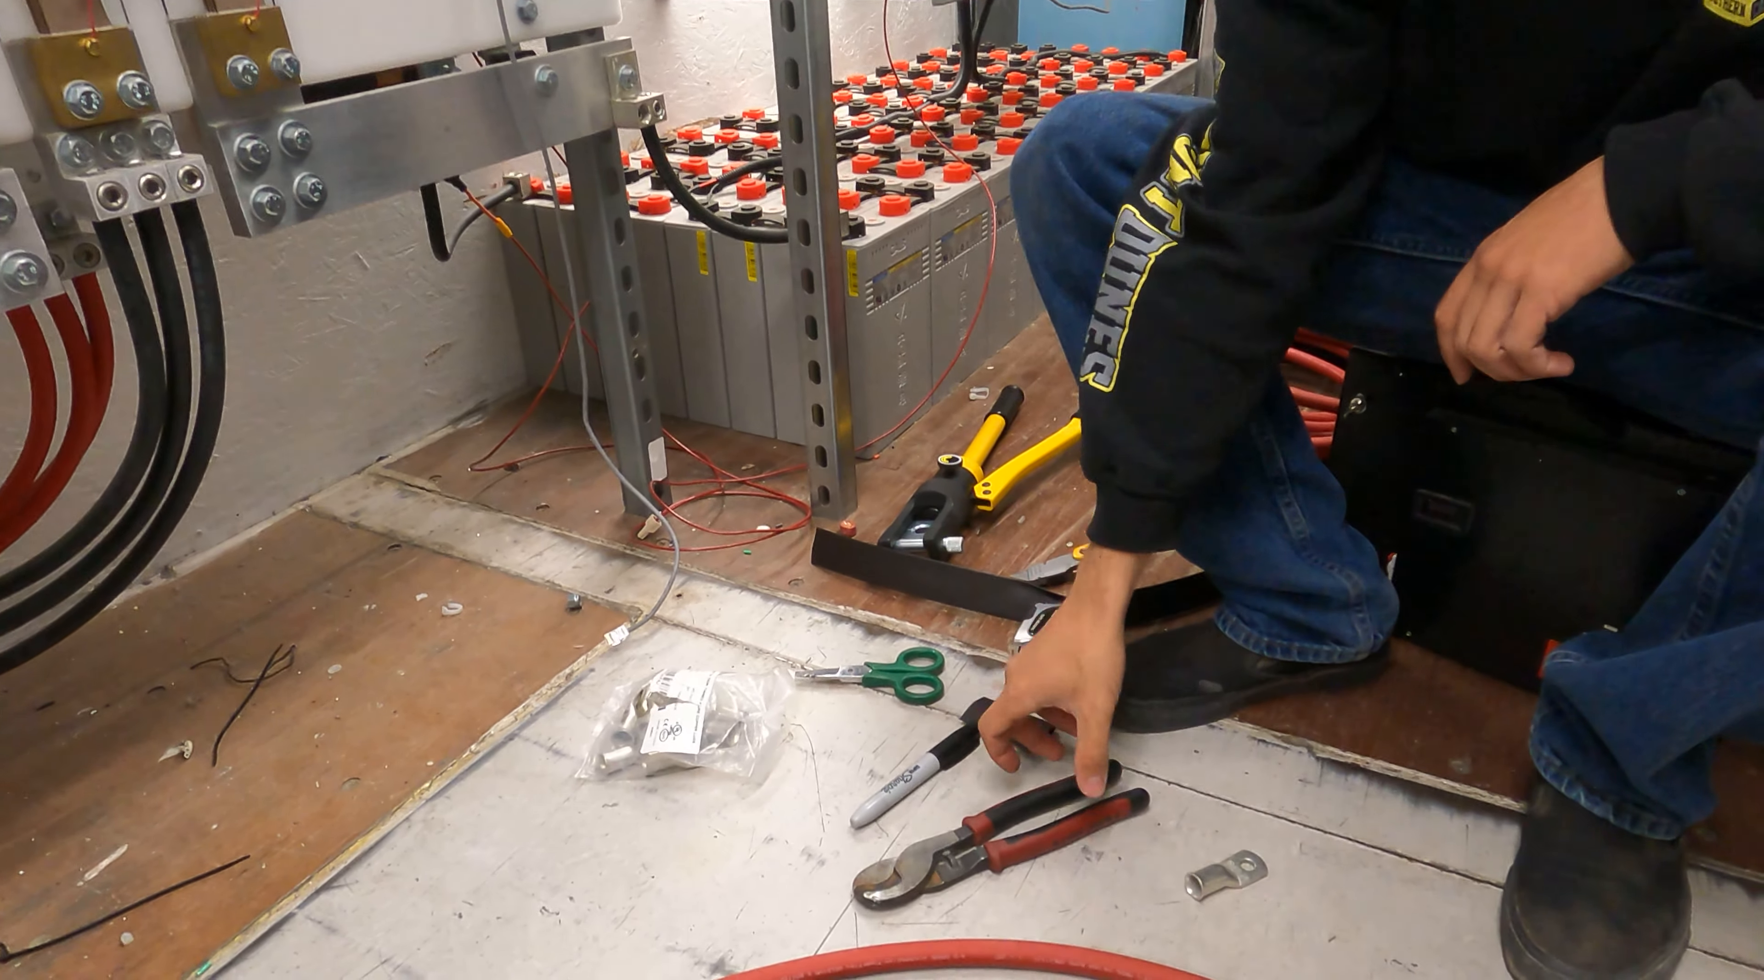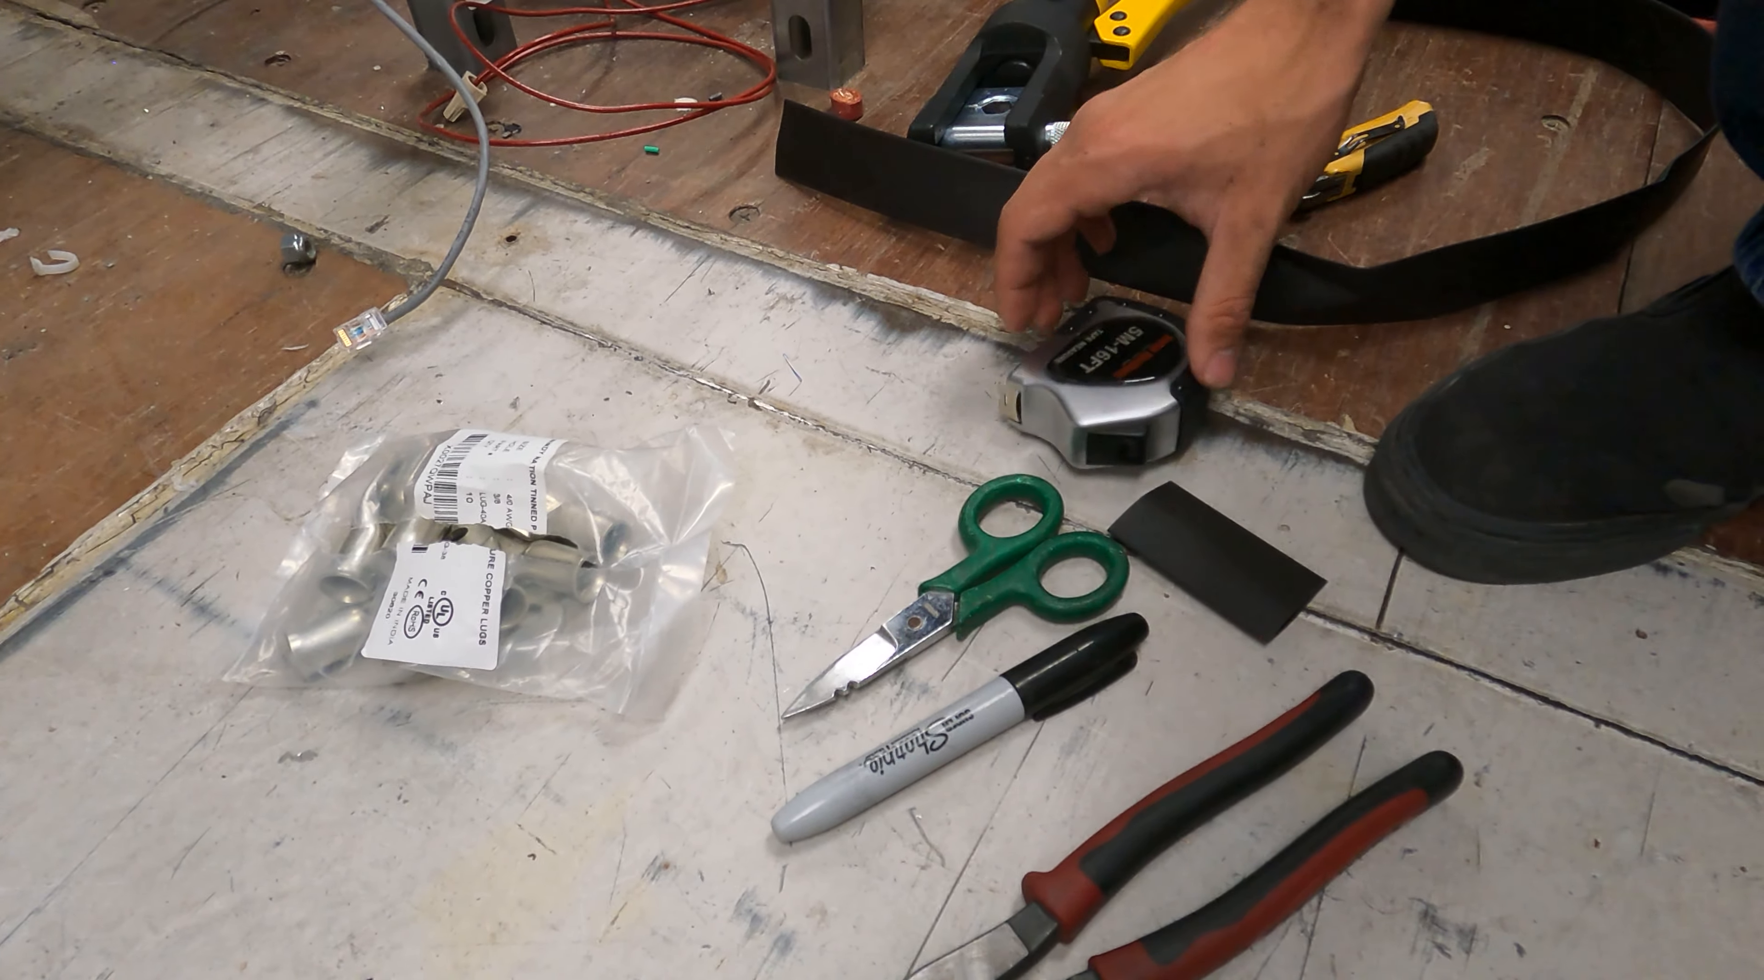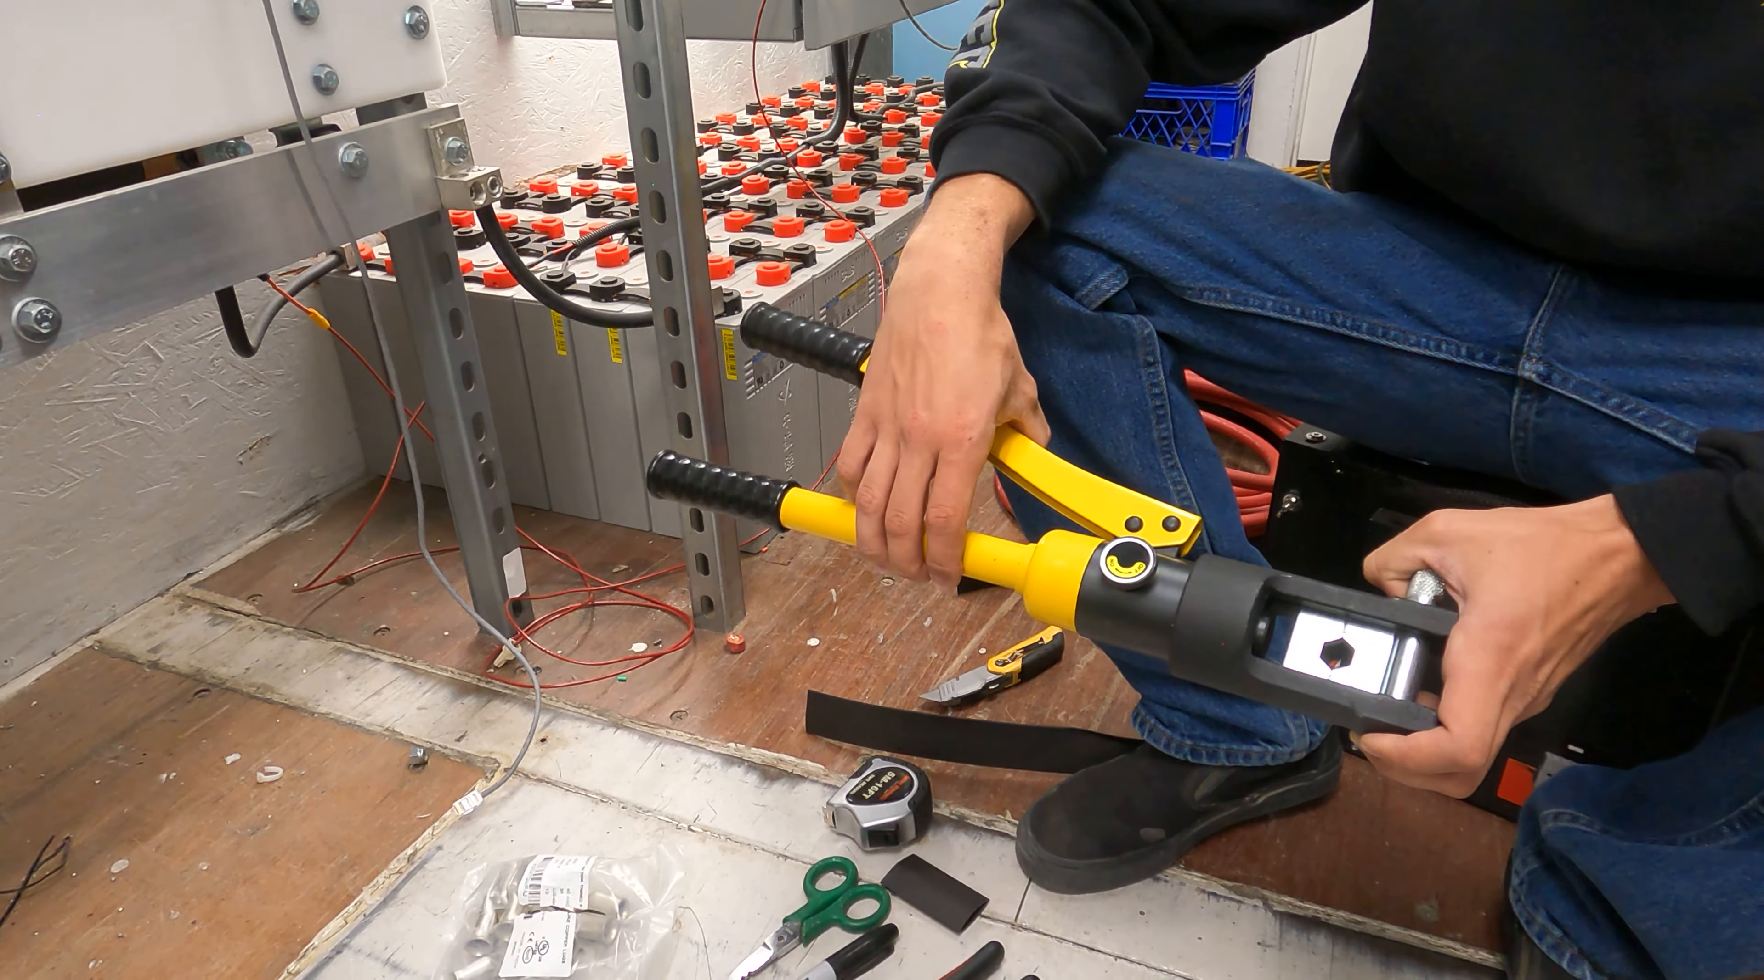First thing, tools you'll need. I have some cutters - this is what I use to cut the battery cable, just a set of Klein cutters. You'll need a sharpie, some scissors if you're putting heat shrink on. I have my lugs in here, obviously. You're going to need a tape measure. This is my bulk heat shrink. And this right here is the most important tool - a hydraulic crimping tool. I got this in a kit on Amazon, about 50 bucks if memory serves correctly. Definitely worth the money.